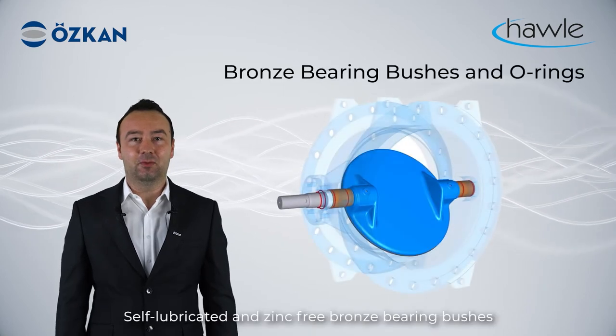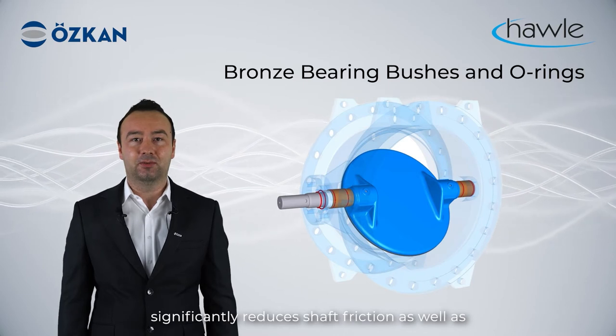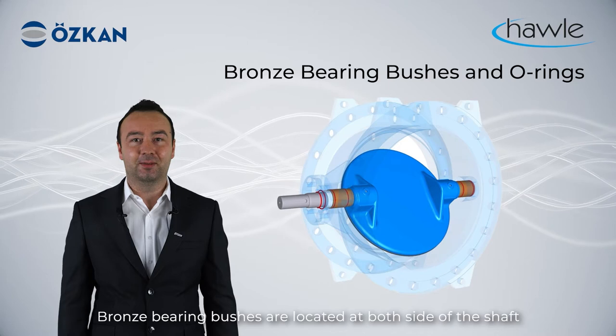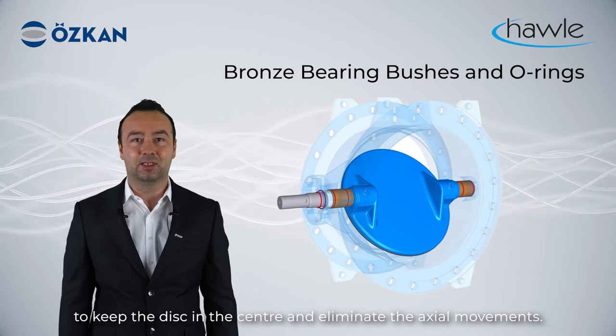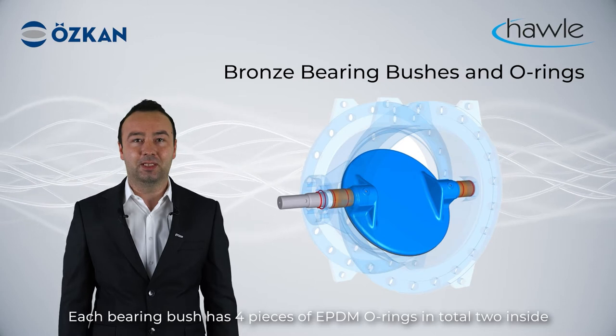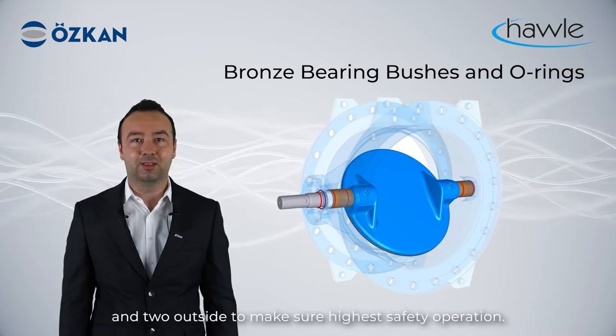The sealing ring can be replaced easily outside without dismantling the valve disc and without any special tools. Self-lubricated and zinc-free bronze bearing bushes significantly reduce shaft friction as well as minimizing the operating torque of the disc. Bronze bearing bushes are located at both sides of the shaft to keep the disc centered and eliminate axial movements. Each bearing bush has four pieces of EPDM o-rings in total — two inside and two outside — to ensure higher safety during operation.